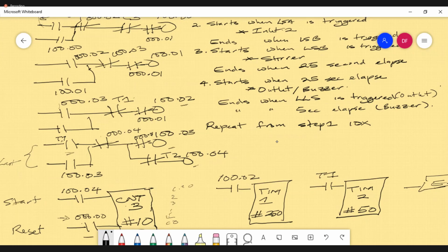I think the start would be more efficient because you don't want to reset it as you start the program. But if you reset it as you start the program, it's still not an issue. But bear in mind that you have to think about the people who operate the system. It's supposed to run 10, and when it runs the 10, the counter is going to stop it, and somebody is going to say, I have to run another batch and press start again.